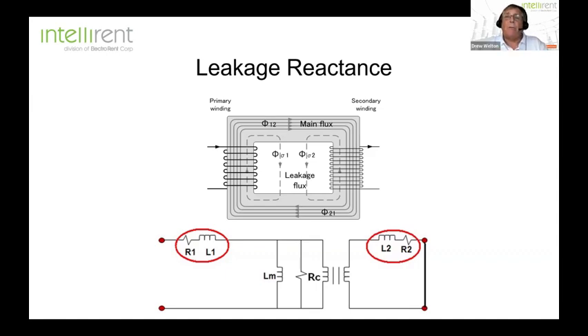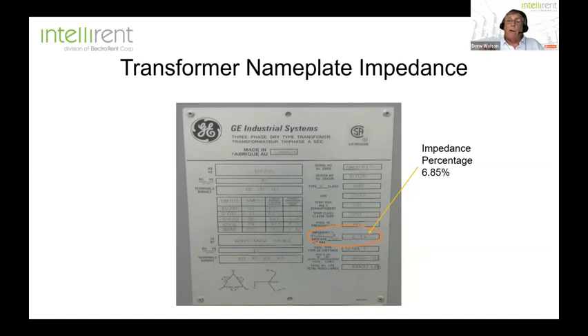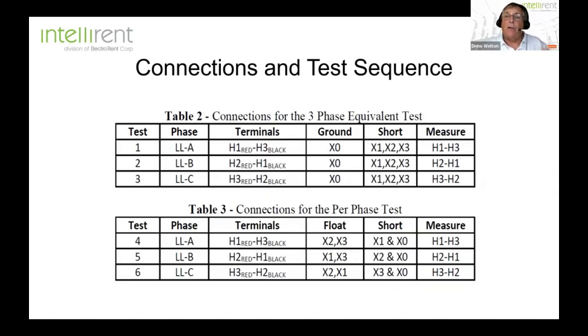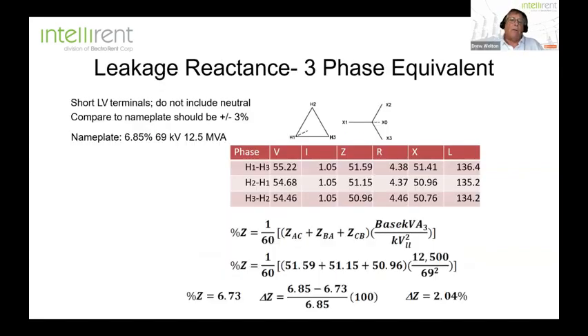When you have physical displacement in your windings, it's going to affect your leakage reactance test and be measured in terms of impedance. But it's very important to understand where to find, on your transformer nameplate, what that impedance is. It's always stamped at the factory, and that's what you want to compare your results to. And here's just a simple diagram that you're going to run. Now, these tests aren't difficult to run. In fact, if you have some multifunction transformer test set like a Megger or an Omicron, or even the accessory to the Doble M4000, you can run this test very easily. It's not that difficult. And why should we run it? Well, there's a number of reasons.